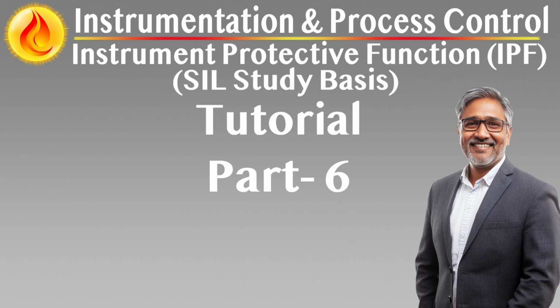Clear data ownership and interface definition. Every communication pathway must be documented in interface control documents, ICDs, including signal direction, data type, purpose, and failure behavior. Ownership of each data element, whether from the IPF, BPCS, or utility systems, must be clearly assigned and controlled.